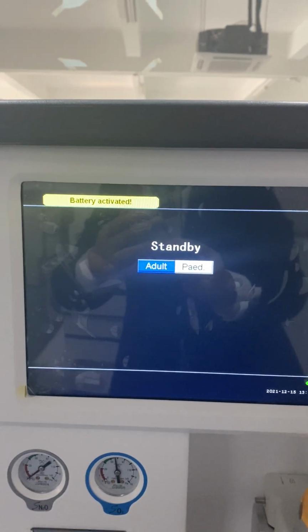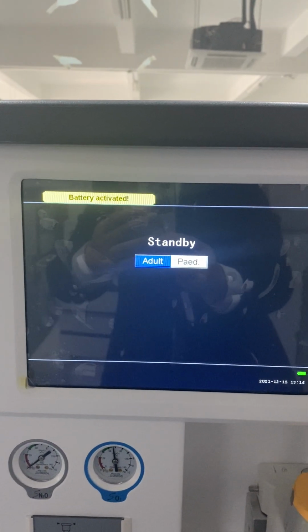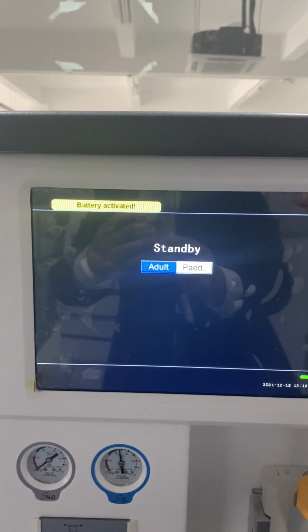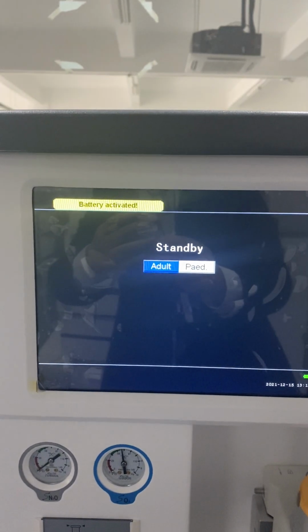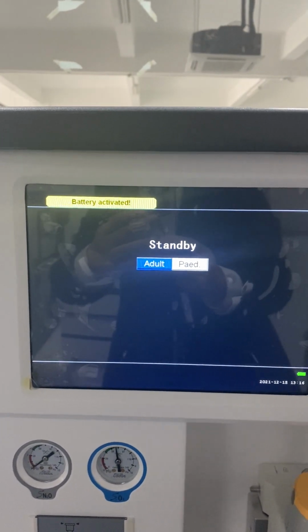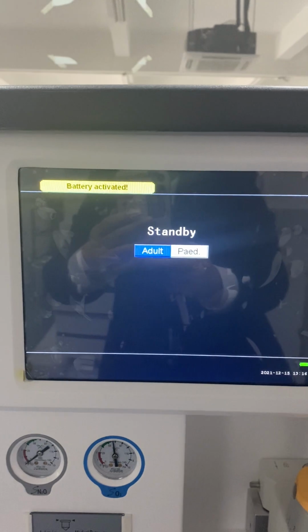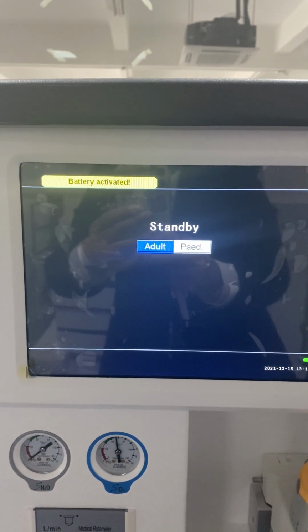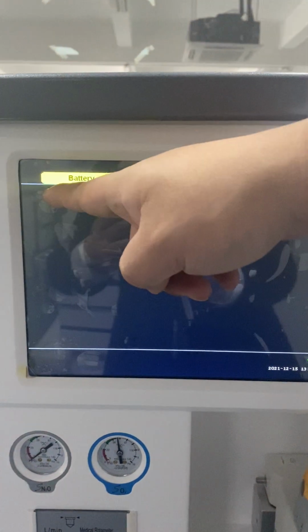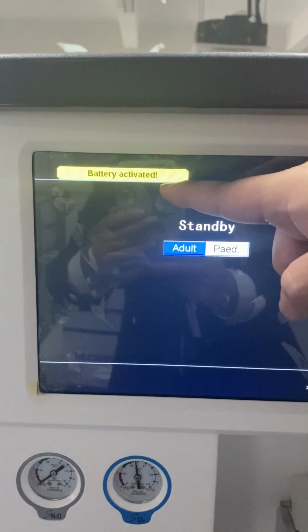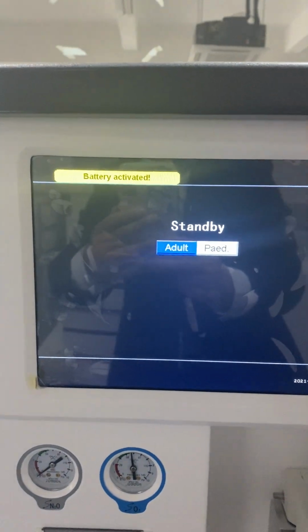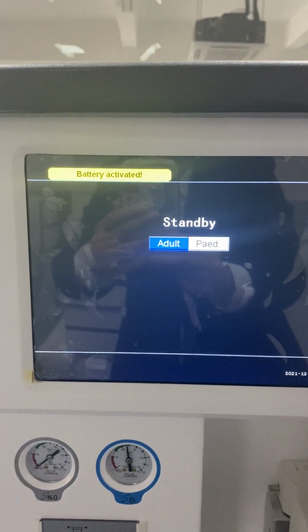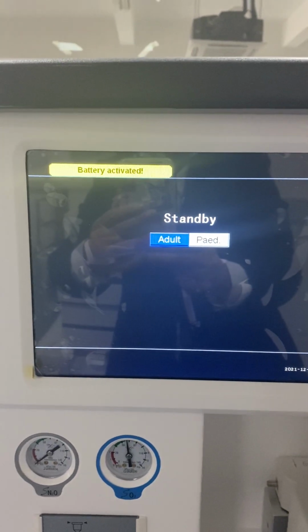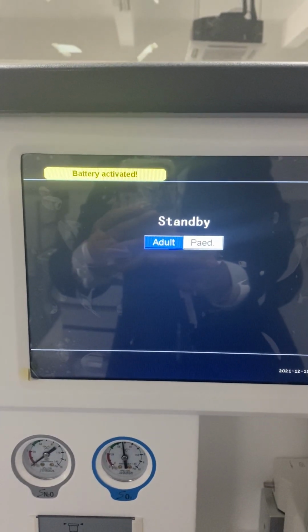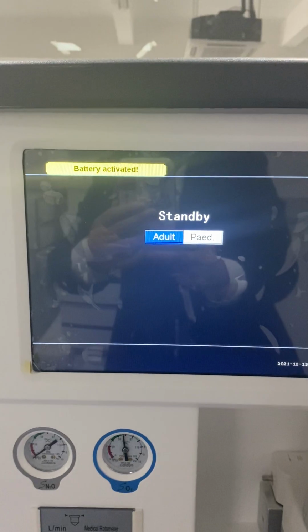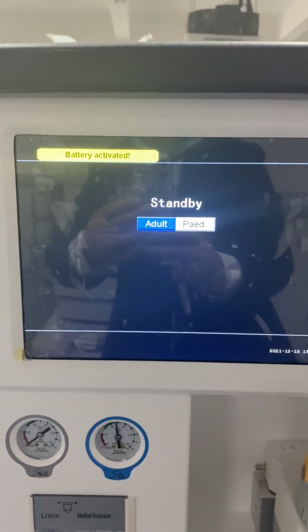Why do we have two colors? If the red color and the yellow color both appear, the red color means the first level and the yellow color means the second level. So the red alarm is the first one we need to solve. By now you can see it is showing the battery activated. It means we are not connected to AC power and are using the battery, but it will not affect the use of the machine because the battery inside keeps the machine usable for at least 3 hours.